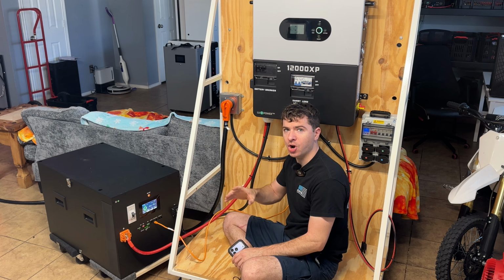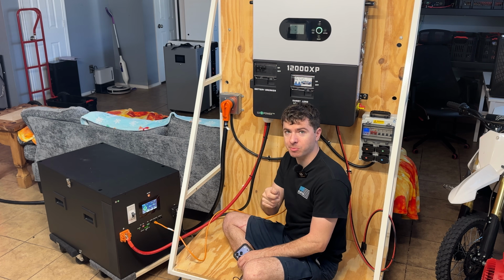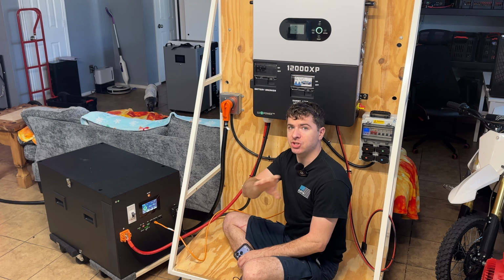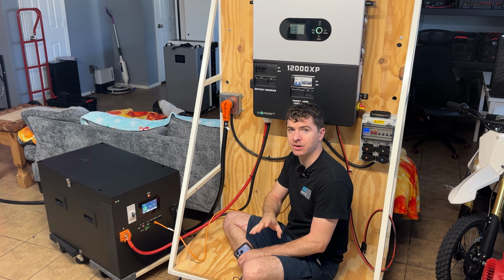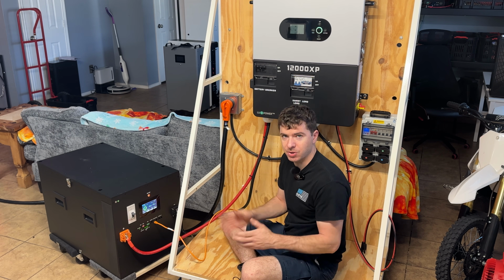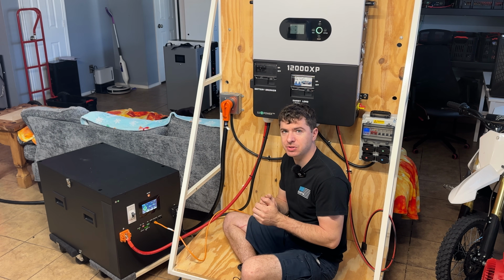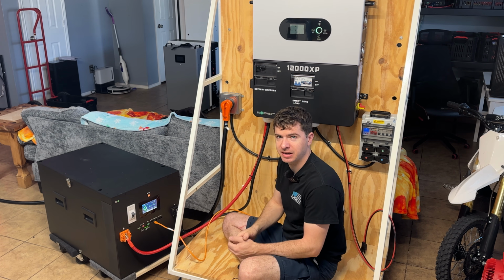While it's running the load, we're actually gonna take the cover off and I'm gonna take a thermal camera and look inside the battery just to make sure nothing's getting hot and doing anything weird. We're also gonna make sure the battery doesn't shut down. So that's it, it should be a pretty tough test to do. Luckily the inverter we have should handle it just fine and everything should be just fine.